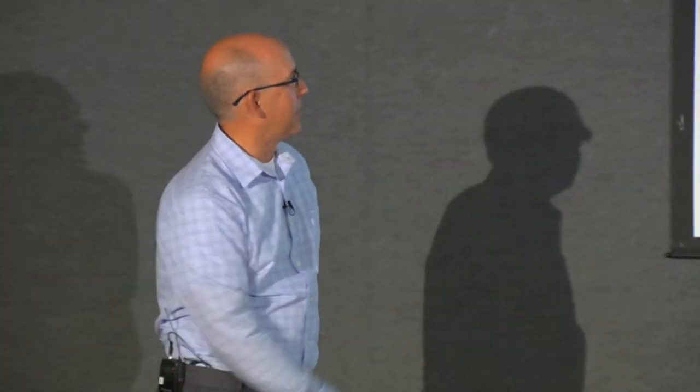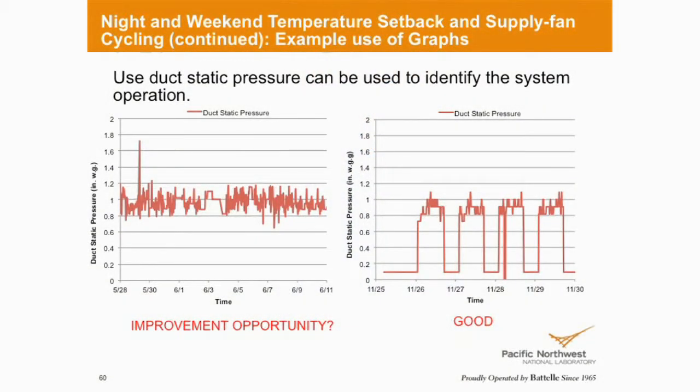It runs 24/7. And over here we can see that it drops down to close to 0, comes up, and then it has a shutdown period. It looks like maybe 6 to 8 hours a day. And that's back in November, and that might be over another holiday period that we call Thanksgiving. So at least it's got a schedule. Whether or not it's following holiday scheduling, we don't know.